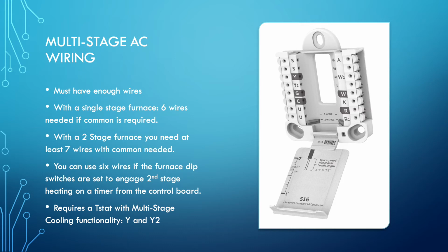They just need the two to provide the power at the thermostat itself, which is going to be your common and your power going up to the thermostat. And that's actually what the secondary transformer powers. It powers the thermostat by itself, or you can have it power the EIM board by itself. Usually I see it wired up for just the thermostat. But in this case, short slide, not a whole lot to go on. You just have to have a second wire for stage 2 cooling. That's it. That's all you need.